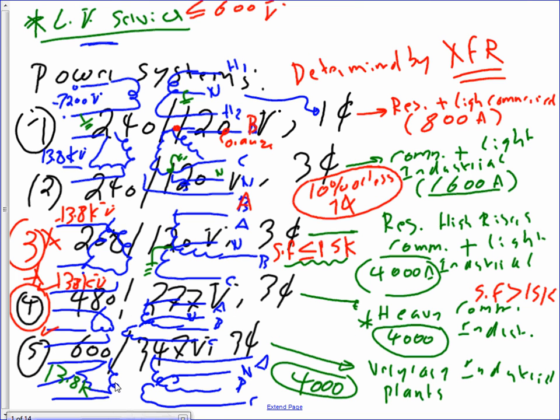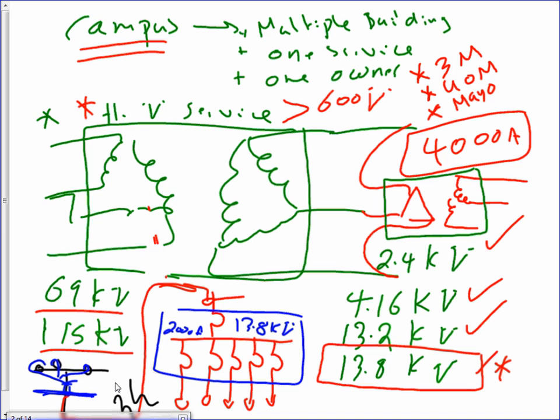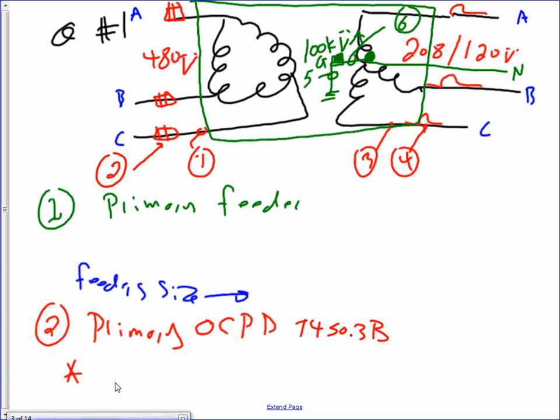Okay, one more time before I go back to the calculation. Here's the power system, secondary, low voltage, the most common, and here's the power system, primary. I took the most common system that you're going to use, very similar to the one that you have, and we're going to do some calculation on it, guys. You guys have a copy of this. I have question number 1. I have a delta-Y transformer, primary delta, secondary Y. The transformer is 480 on the primary, 208/120 on the secondary, and I need to size the primary conductor coming to the transformer, the primary fuses, the secondary conductors, the secondary fuses, as well as the grounding electrode conductor and the main bonding jumper.